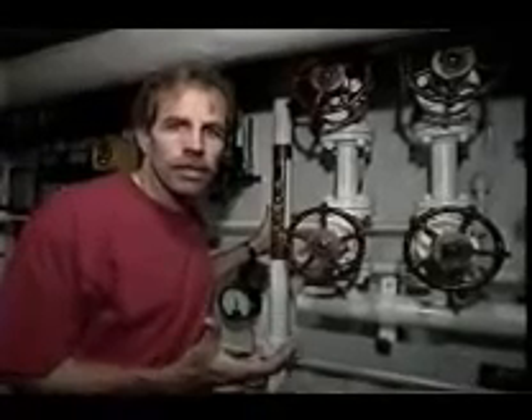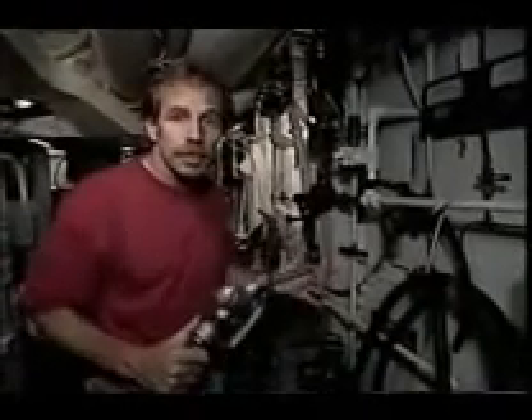There are many different techniques that can be used to measure fluid flow, and I'd like to first talk about those techniques which are commonly used in constrained systems such as pipes. Now, in a constrained system, you don't need to know about the direction of flow. All you really need to know is the magnitude. One common technique that's used in fluid delivery systems, such as gas pumps or this oil pump here in the engine room of the Albatross, is a positive displacement flow meter. And there's a positive displacement flow meter right down here in this system.